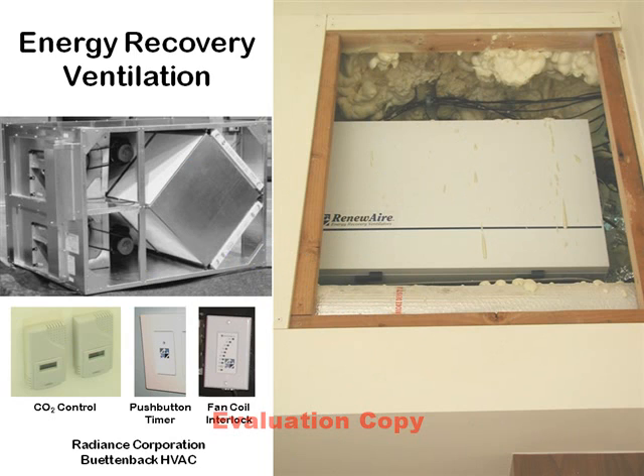Energy recovery ventilation is used to precondition outside ventilation air using heat from the exhaust air stream. The exchange of heat takes place in a special cross-flow heat exchanger. The energy recovery ventilation comes on to exhaust bathrooms whenever a user operates a push-button timer. A fan coil interlock control also brings fresh air into the home at a set percentage of the time, and a CO2 control in the living room controls the ERV dynamically in response to changing carbon dioxide levels due to changes in occupancy.